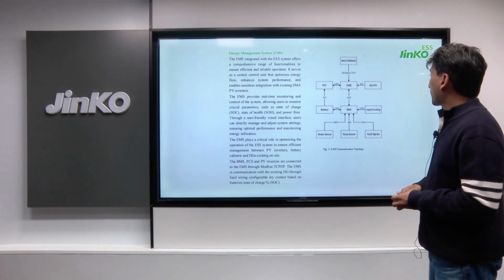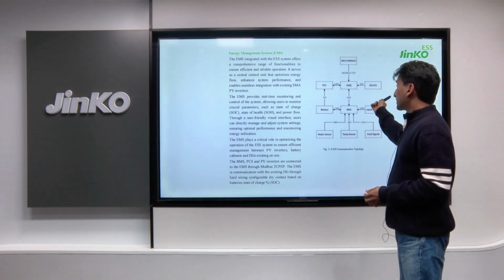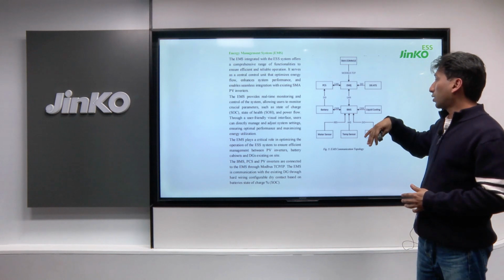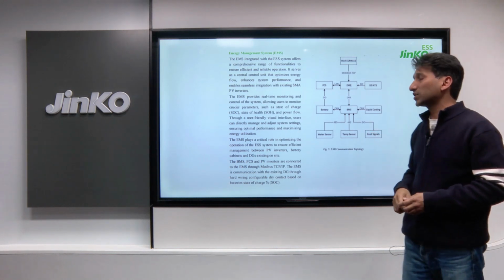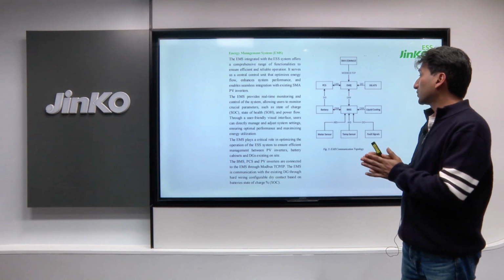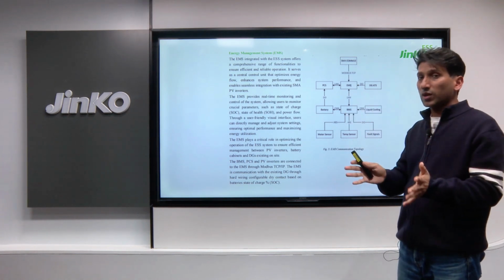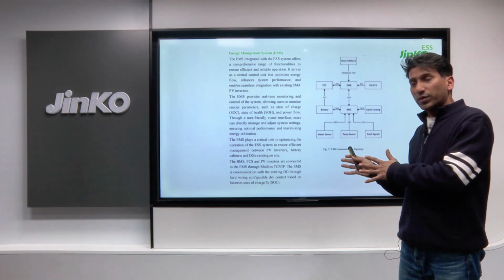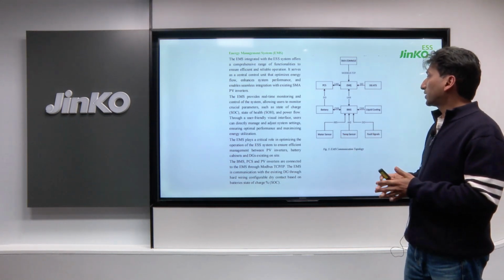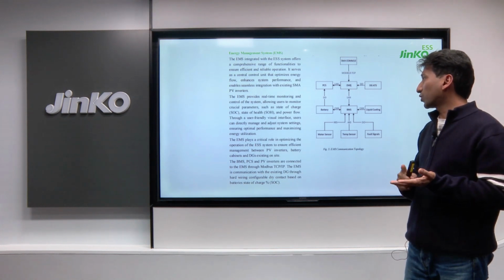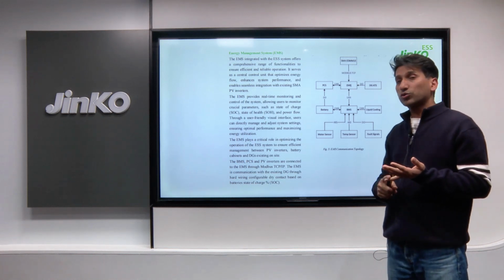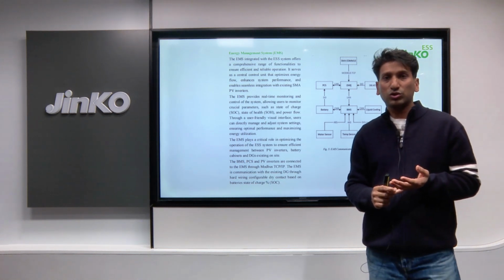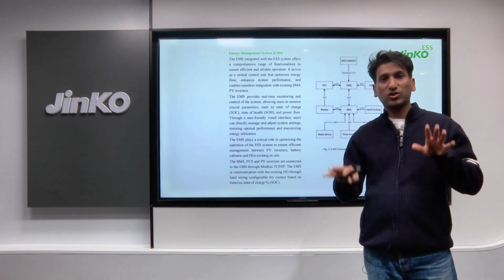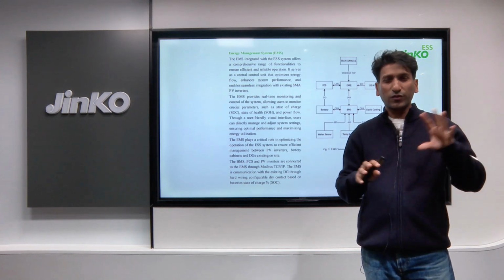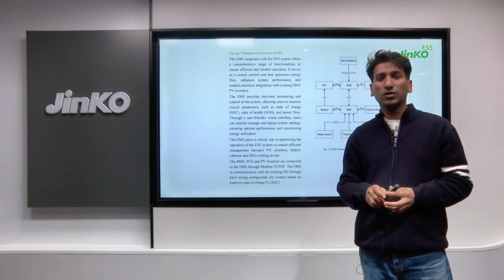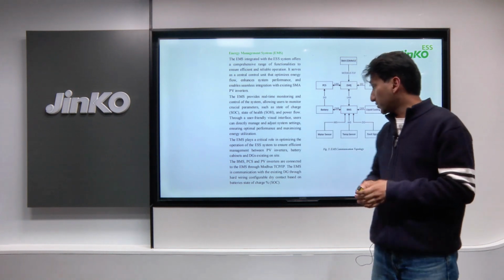That EMS is installed and connected to the diesel generators, the PCS, and the BMS side of the battery. This EMS provides real-time monitoring and control of the whole system, for the batteries, the PV inverters, and the PCS. It can monitor the state of charge, state of health, and the power flow, and it can also be configured to optimize the power from the different sources, so that the whole system can be optimized.